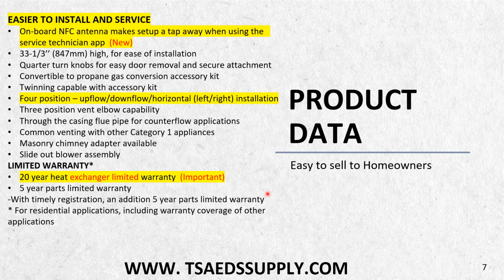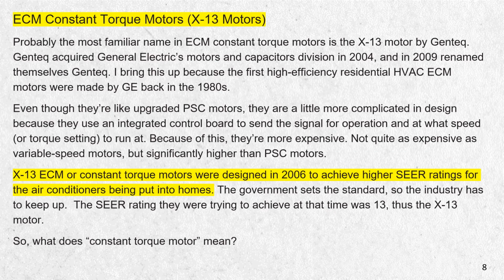It's very important you see that they can deny a warranty on a heat exchanger if it's not installed correctly. And we need to look at this. A lot of times, I've been out in the field on like 90 calls, and one of the 90 calls was actually installed correctly, like the install manual says. So most people don't even look at the install manuals anymore. They just throw them off because they've been doing it 20 or 30 years or whatever. That's not the case anymore. So we have to look at those install manuals.